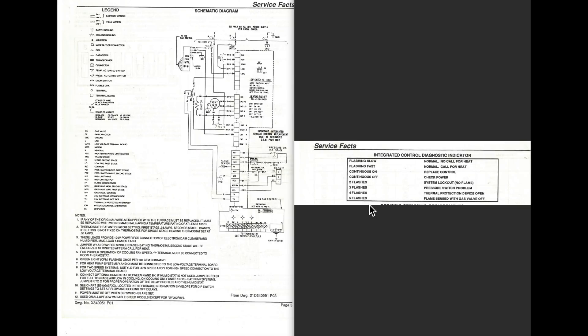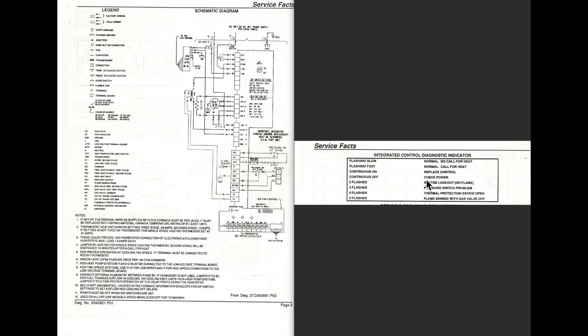The different flashes for different codes. Two flashes means the system is locked out, no flame. That means this thing is tried three times to light, and it has not lit, and so it locked out. These will usually start again in about an hour and try again, and they'll run three times again. So there could be, for whatever reason, it either doesn't have gas to it, something's broken, flame sensor isn't sensing flame, igniter's not lighting, something like that.